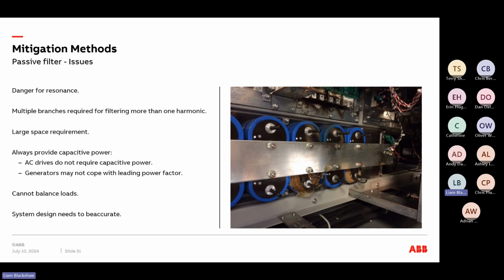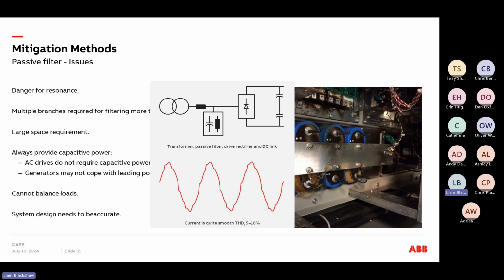So yeah, there's a danger of resonance as well. You've got things like multiple branches required for filtering more than one harmonic. You also need a large space, and they always provide capacitive power where AC drives do not require capacitive power, but generators may not cope as well with a leading power factor. Passive filters can never balance loads, so you need to have an accurate system design, but also you need to be aware that if anything changes in that network, you can cater for that as well. But in fairness, you do get a good level of harmonic clearance, where your total harmonic distortion can be something along the lines of that, at least anyway.